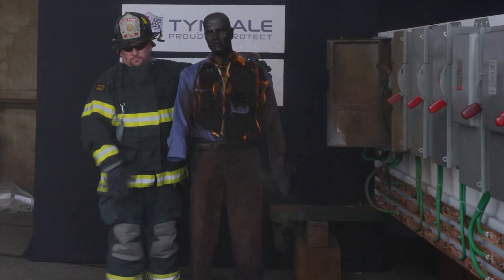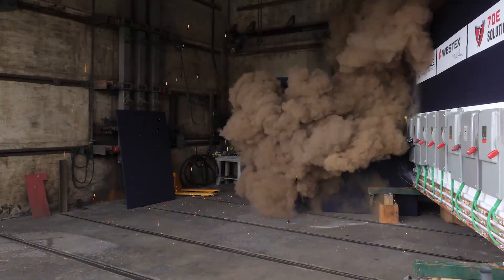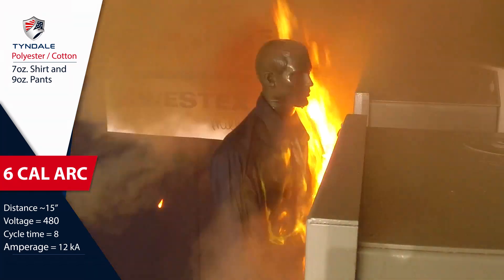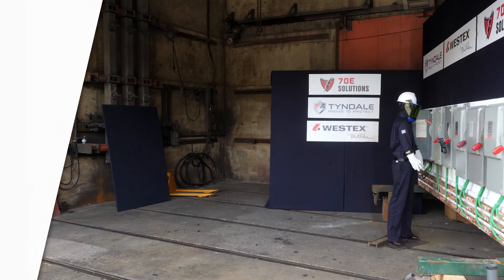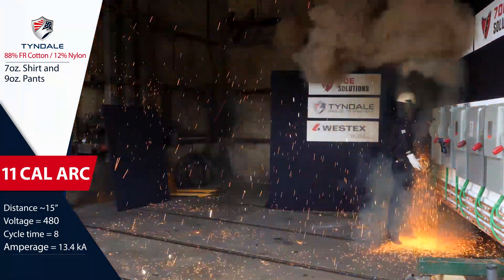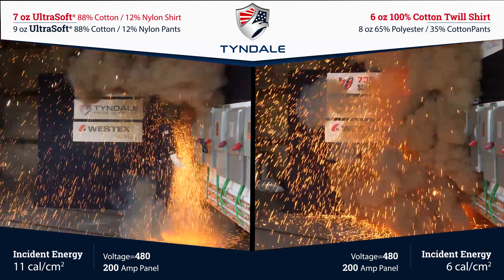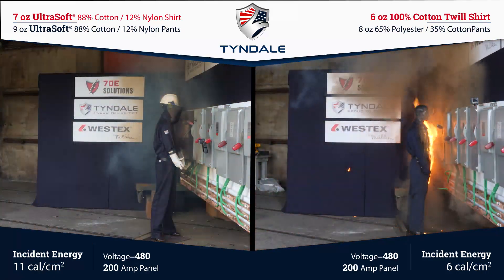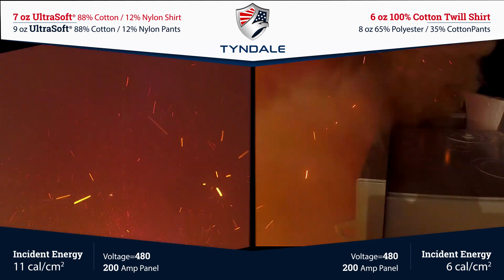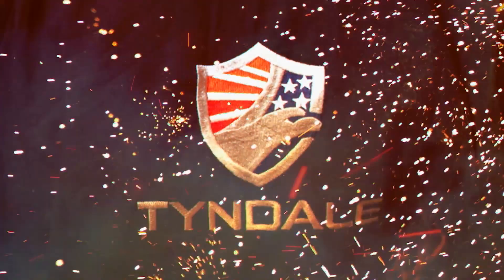Regardless whether the fabrics are blends or 100% cotton, we created arcs with no mannequins to fully capture the projection of the energy, with mannequins wearing 100% cotton, poly cotton, or other non-FR clothing, and with mannequins outfitted in Tyndale flame-resistant clothing — both new and after 100 industrial laundrings. This testing clearly demonstrates that if you work on or near energized parts or equipment, flame-resistant and arc-rated apparel can and does dramatically reduce injuries and save lives.